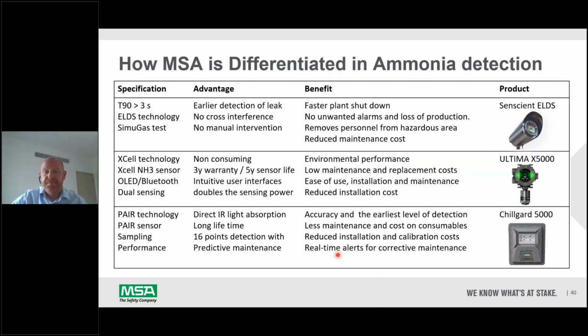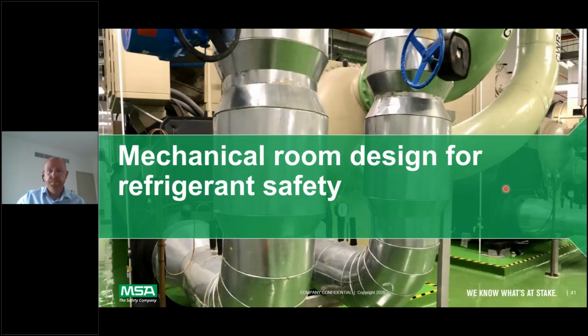So this is a summary really of the 3 types of gas detection system we offer, for ammonia and sometimes for the other gases. For HFCs, it's HFCs and freons. It's mostly the Chilgard 5000, but for the ammonia and any of the other more dangerous gases, we can offer the open path gas detection, or we can offer our long life X5000 point detector. So how do we design these mechanical rooms for refrigerant safety?